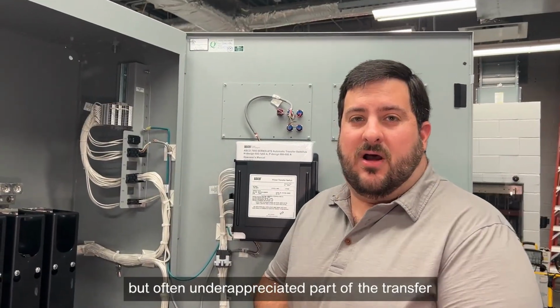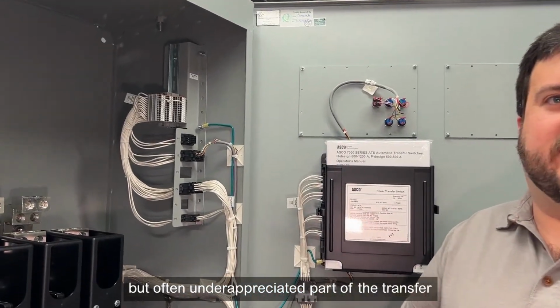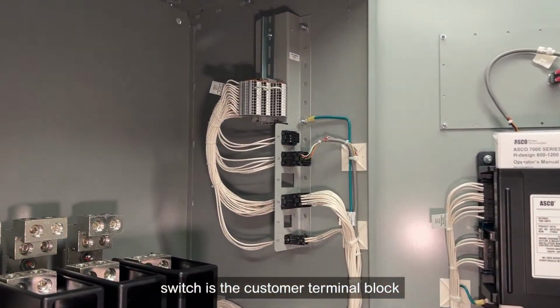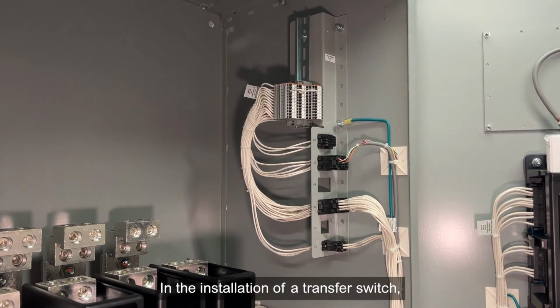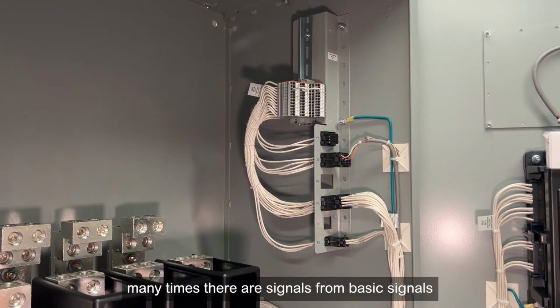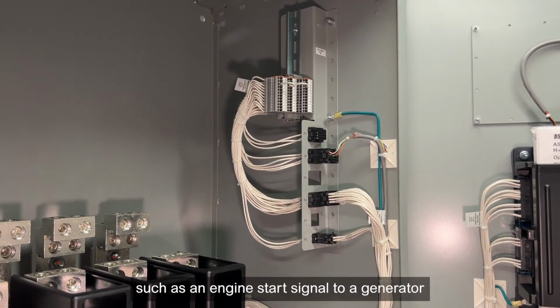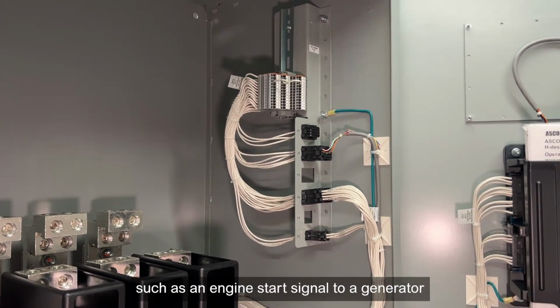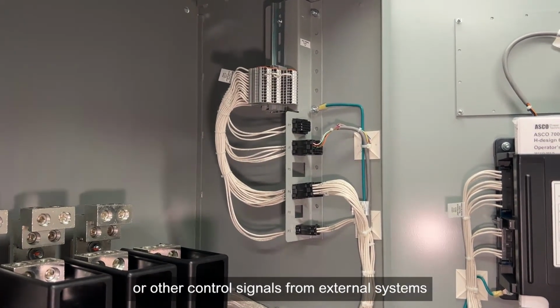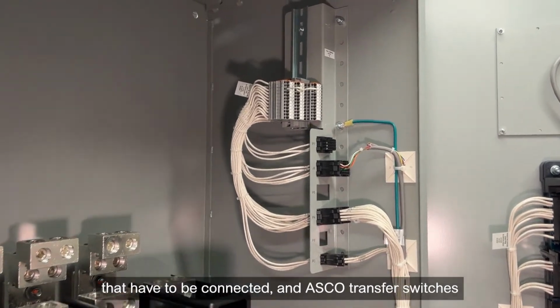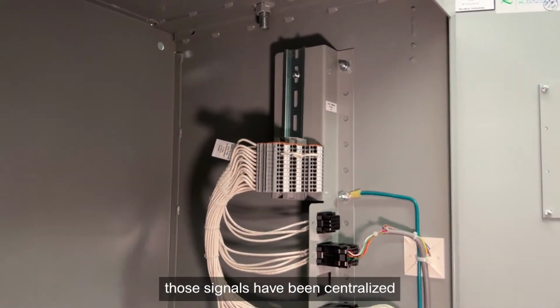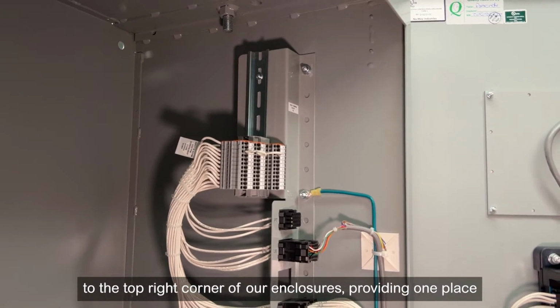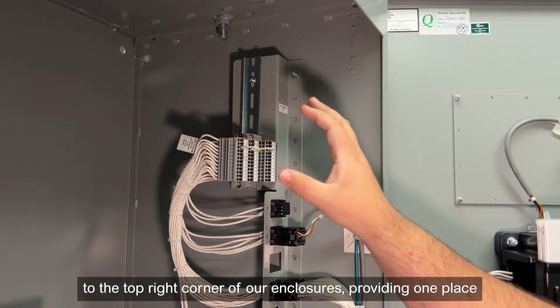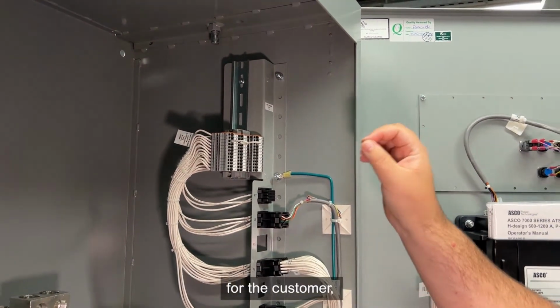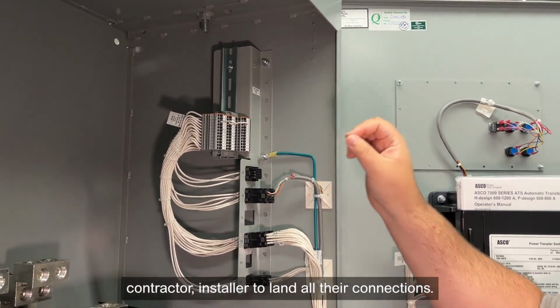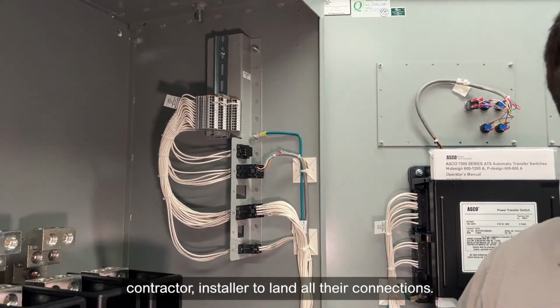A simple but often underappreciated part of the transfer switch is the customer terminal block. In the installation of a transfer switch, many times there are signals from basic signals such as an engine start signal to a generator, or other control signals from external systems that have to be connected. In ASCO transfer switches, those signals have been centralized to the top right corner of our enclosures, providing one place for the customer, contractor, and installer to land all their connections.